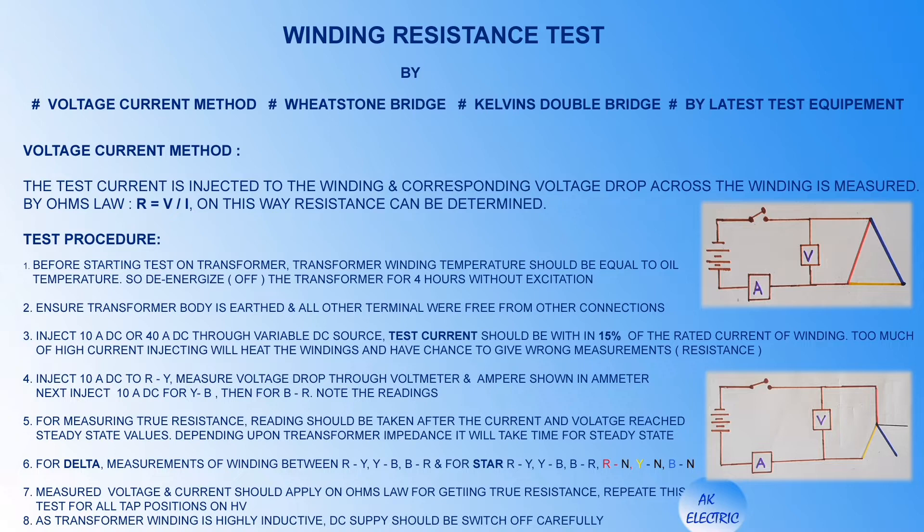Inject 10A DC to R-to-Y. Measure voltage drop through voltmeter and ampere shown in ammeter. Next inject 10A DC for Y-to-B, then for B-to-R. Note down the readings. For measuring the true resistance, readings should be taken after the current and voltage reach steady-state values. Depending upon the transformer impedance, it will take time to reach steady-state.